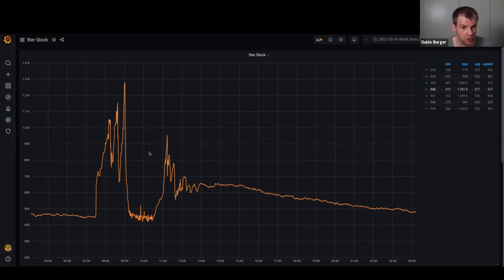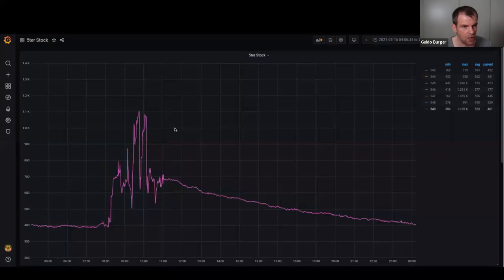What's our recommendation? We need to open the windows a little longer, maybe not just 5 minutes, maybe 10 minutes, to really make an efficient ventilation situation. That's what the inside of the data plots is showing us. Another situation, again you see the ups and downs. This is not what we want to see. We want to see a clear drop of the value to fresh air. We want it to stay there for 5 to 10 minutes and then see how the situation is, and maybe even keep the window open for more time, depending on what is happening in the classroom.